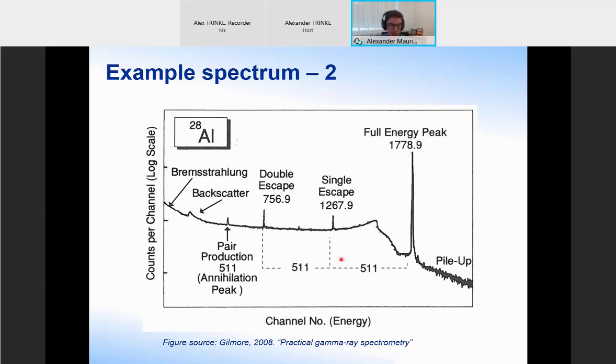So in addition to the Compton edges, the full energy peak, and the pileup, you now have these escape peaks, which you'll see here. There's a single escape peak, exactly 511 keV below the full energy peak, where one of the annihilation photons escaped our detector before it deposited its energy. There's also a double escape peak, exactly 1022 kiloelectron volts below the full energy peak.